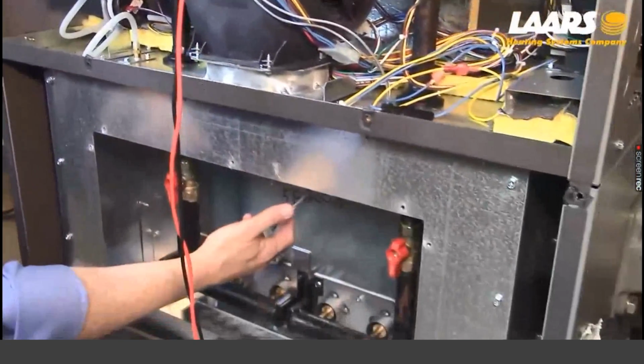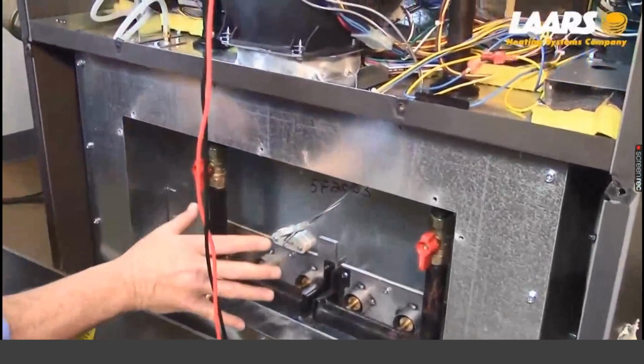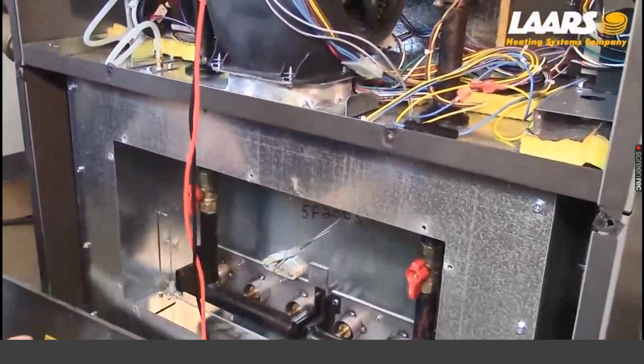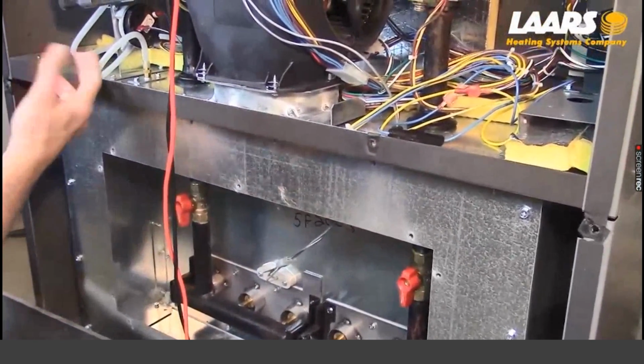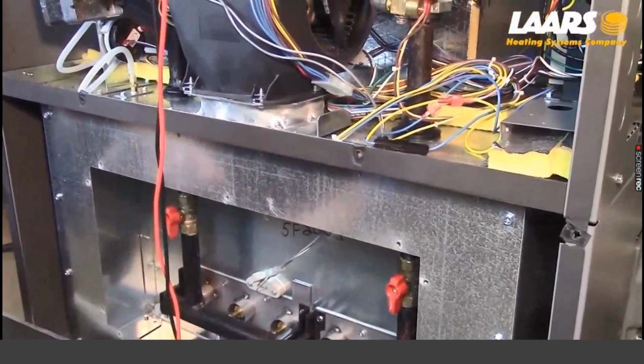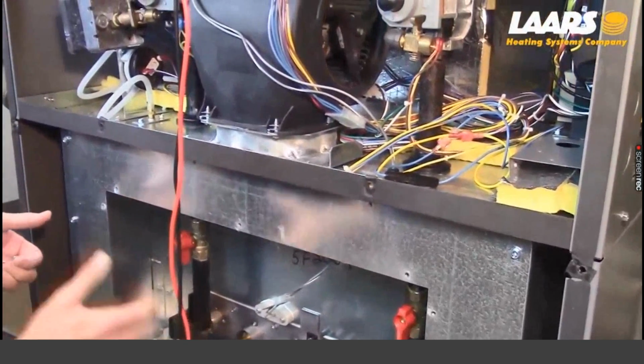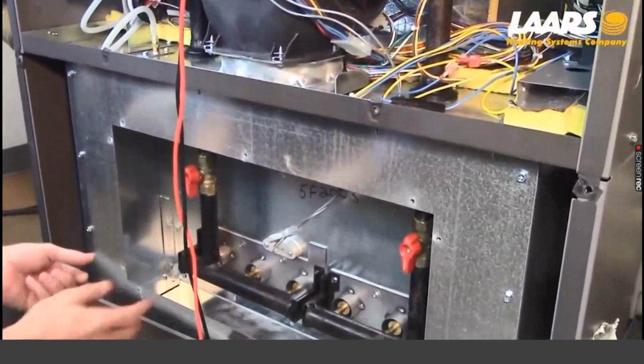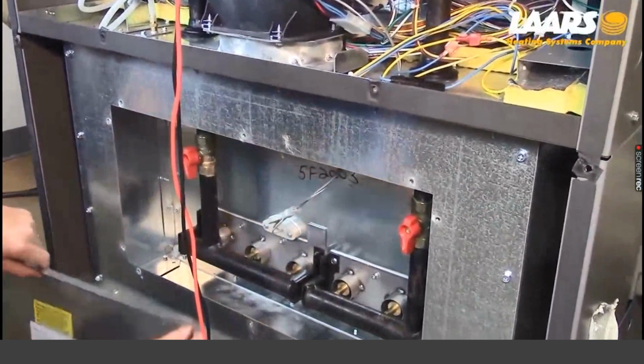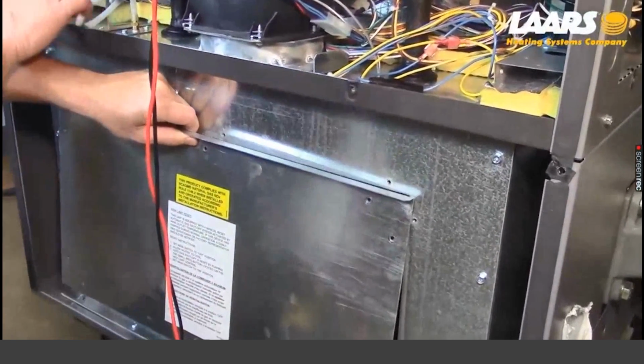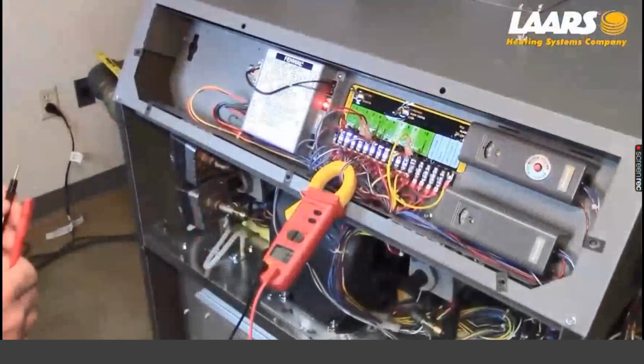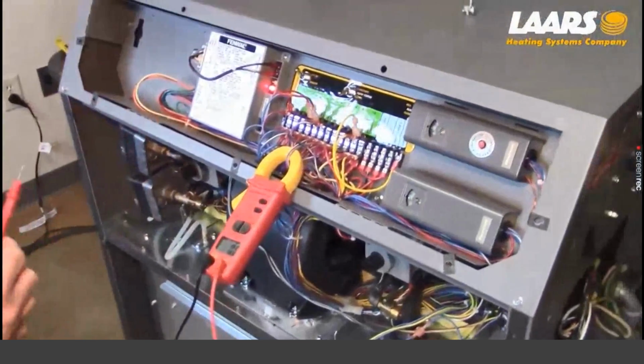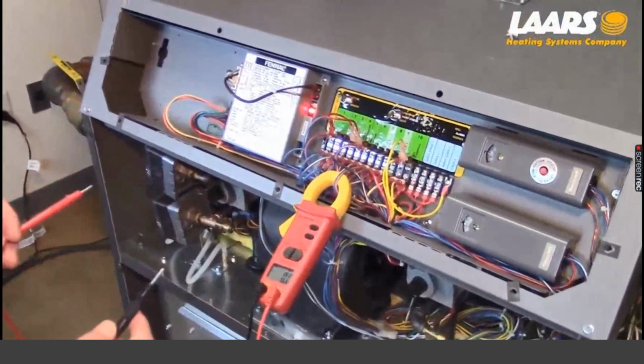replaced igniters, and then they want to test the boiler. This cover has to be on, or all of your air pressure is coming out here, and therefore your pressure switch won't make. Also, when putting it back on, put all of the screws back in, because if I only put 2 screws in, I've got air gappage on the bottom, and all that air pressure is going to come out, and it will not make the pressure switch. So make sure this is back on tight. Okay, so again, we've then checked the proof of fan.